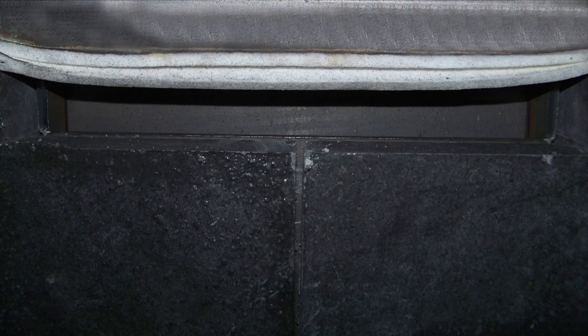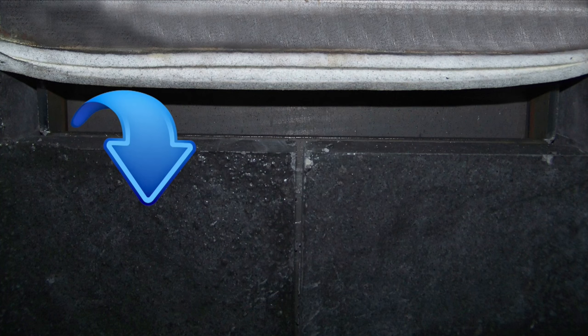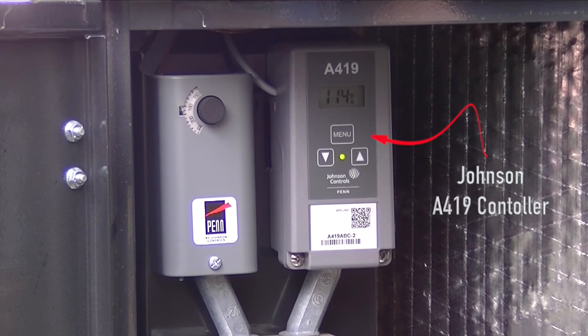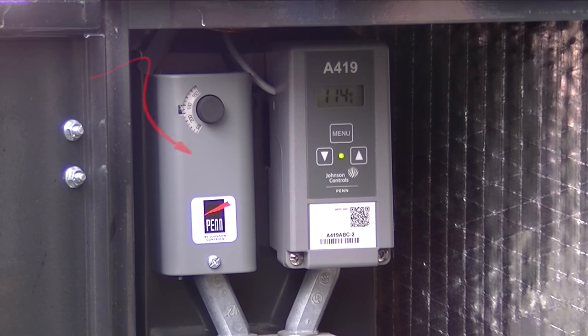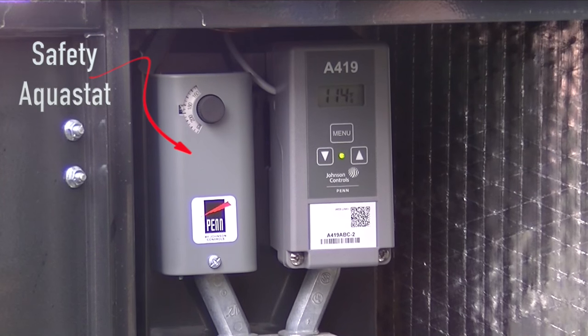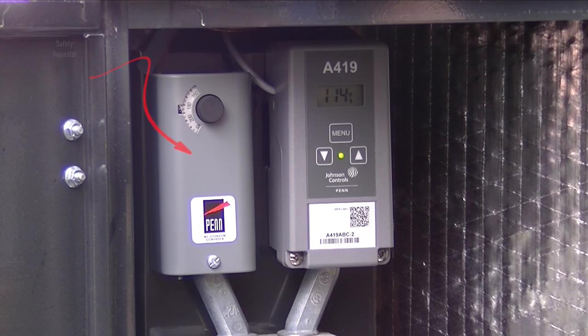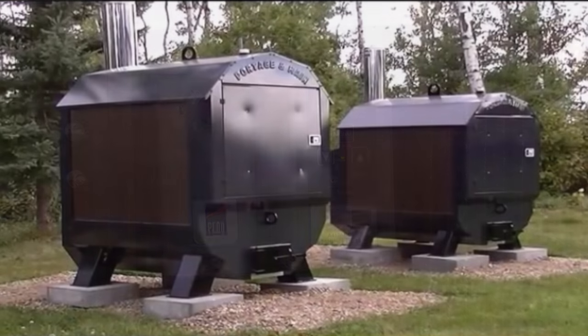We also add air above the fire, which is very beneficial for complete combustion. As a bed of coals is developed, more air is introduced above the fire, which is now in stage two combustion, achieving a cleaner, more efficient, complete stage two burn of the smoke and gases. Reliable digital Johnson controls regulate the temperature and are programmed to within one degree. A high limit safety Aquastat ensures that in the unlikely failure of a Johnson control, the furnace can be controlled with this manual Aquastat.